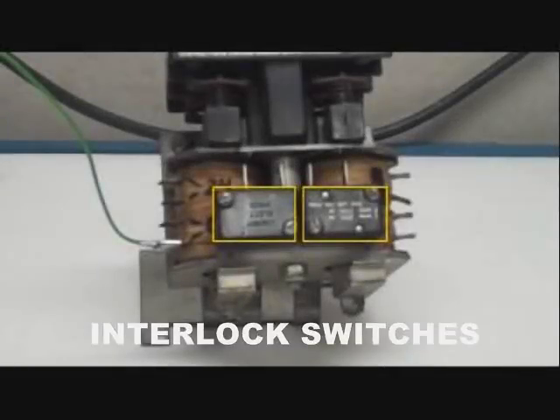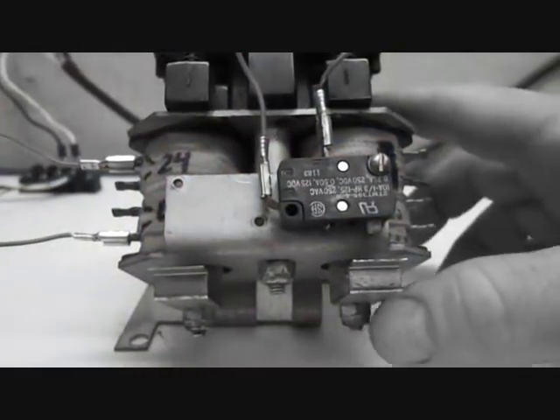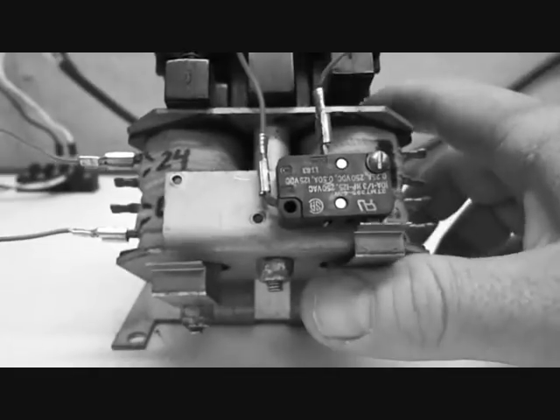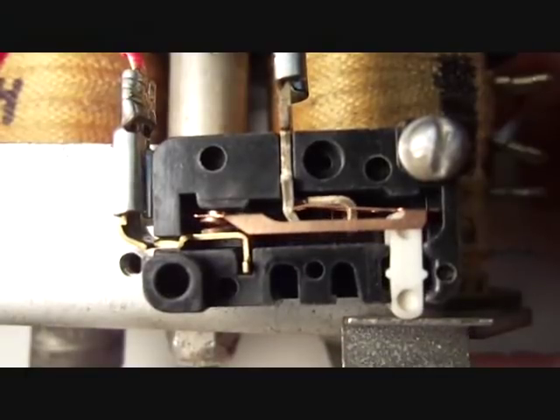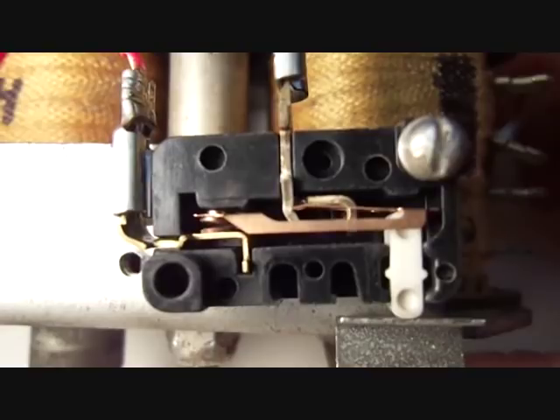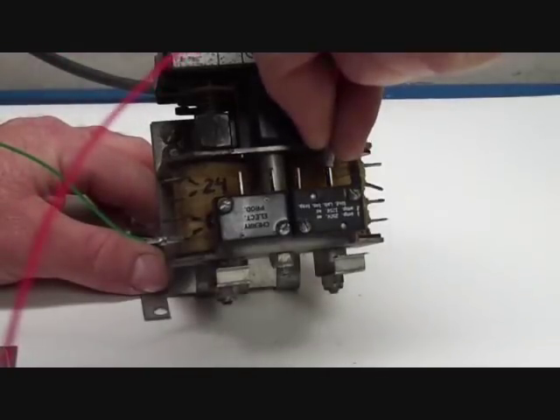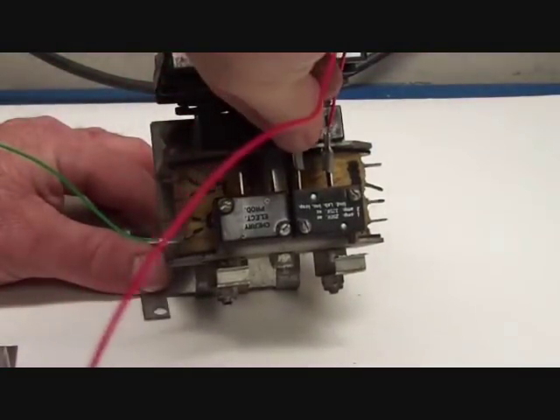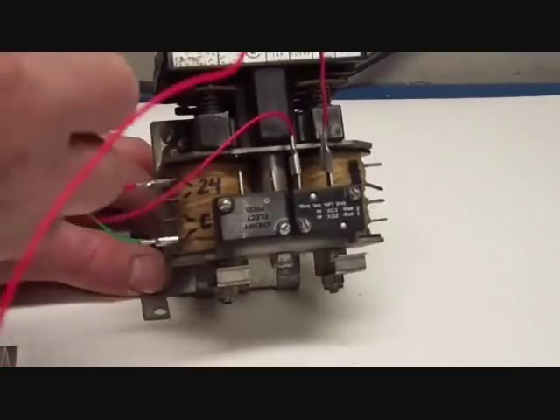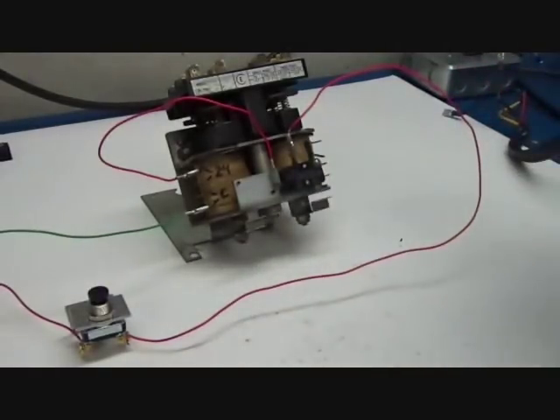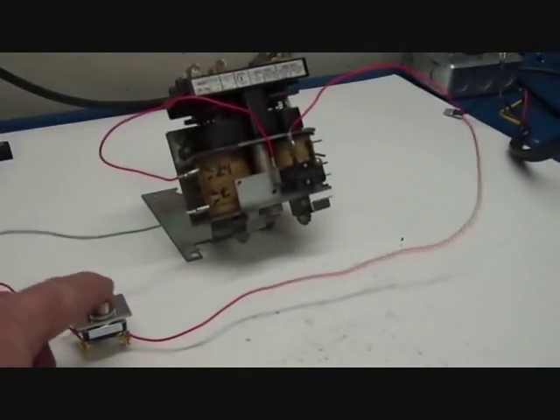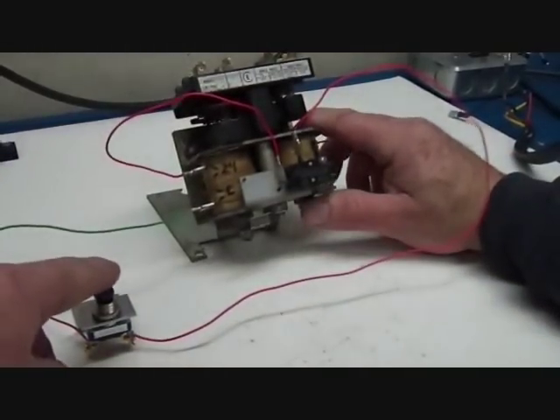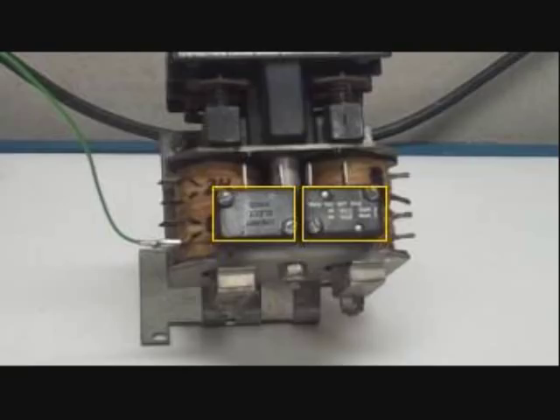As another layer of protection, they might also be electrically interlocked. The right side of this contactor has a normally closed switch that opens whenever the coil pulls in. The 24 volts that activate the left side coil go through this switch, so whenever the right side of the contactor is pulled in, it interrupts any voltage going to the left side coil. There's one of these interlock switches for each coil.